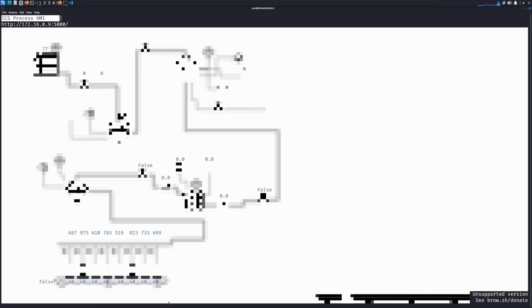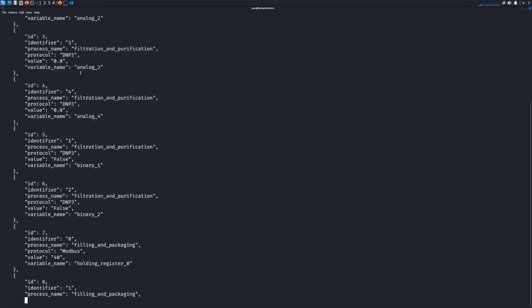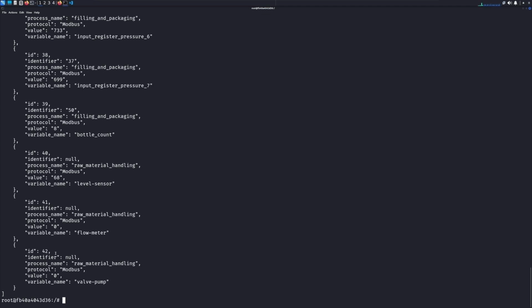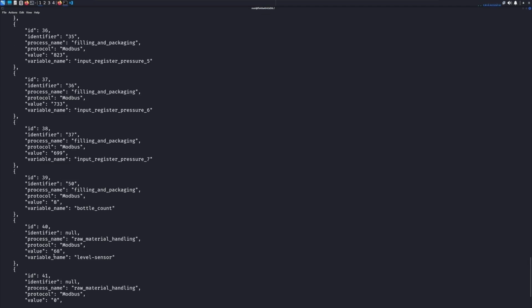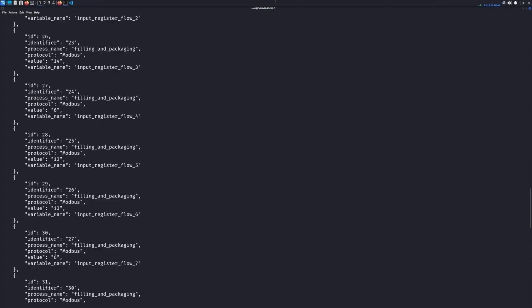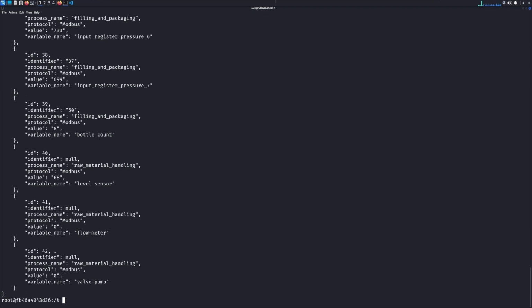Browsing the IP and port on the terminal with the help of browsh. There is a value changing at the start of the figure. Again, getting the JSON data to check which value is changing with respect to the JSON. There is a process named raw_material_handling with protocol Modbus, where the value is changing. Check it again to confirm.